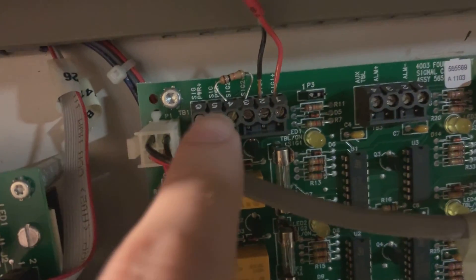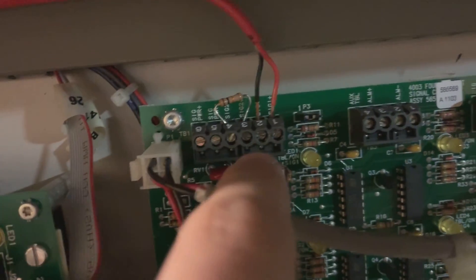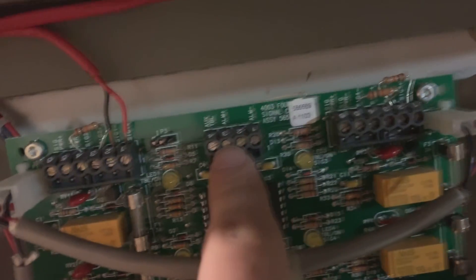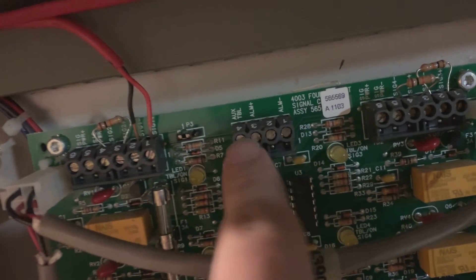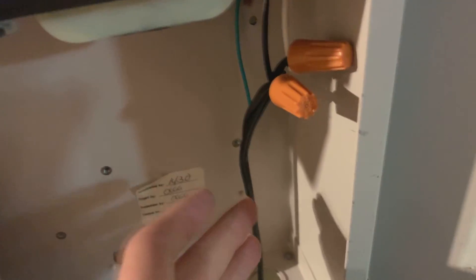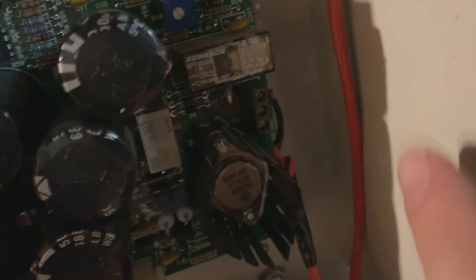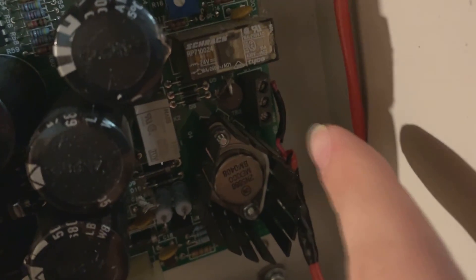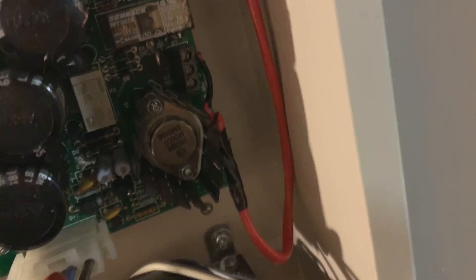This is our speakers out. So you can see here we got our speaker circuits. This is our relay stuff. Speaker circuits here. Most of them are resistored out. This one just continues up and goes out to power our speakers. And over here we have the power supply board. And of course we've got our power coming in right down here. This wire, this negative wire, is actually running to the auxiliary negative on the 4010. If that negative wire isn't there, it won't work. I learned from experience because I'm not thinking.